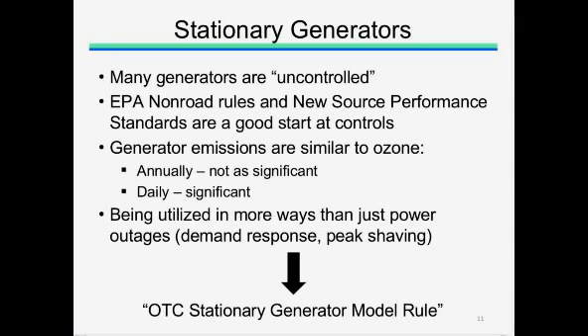Because ozone is episodic, daily emissions are a concern, and for a generator, its daily emissions can be significant even if its annual emissions are small. Additionally, there is more interest than ever in using generators for other purposes, other than just for power outages, such as demand response and peak shaving. The additional emissions from these types of non-emergency use can be detrimental to air quality.